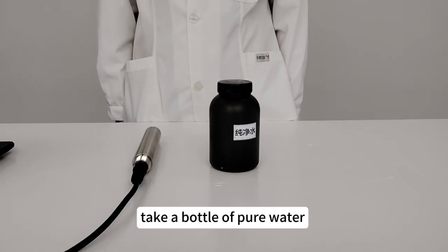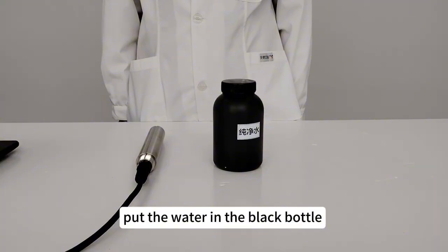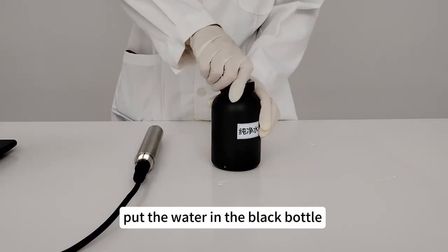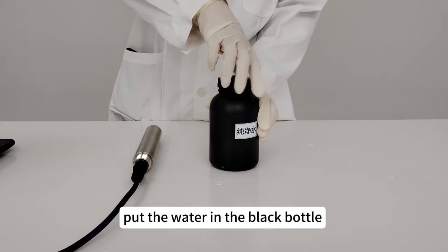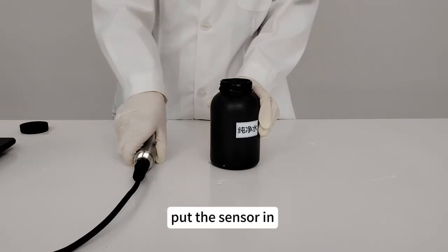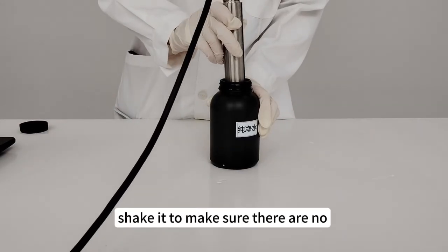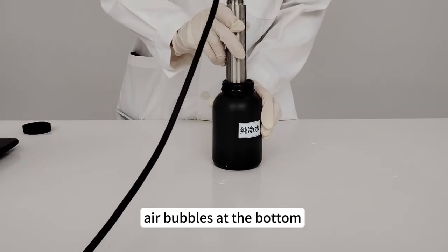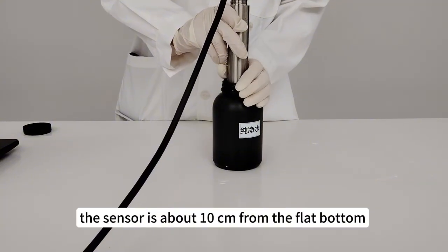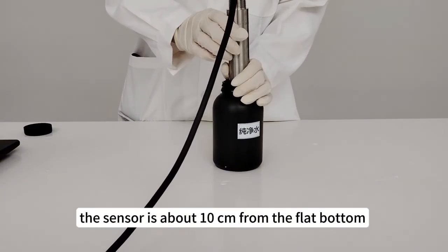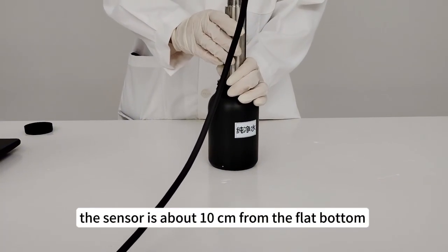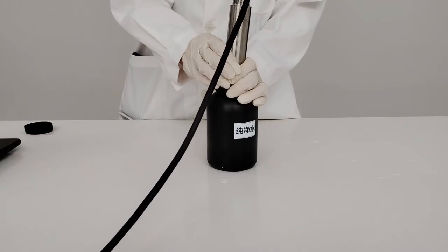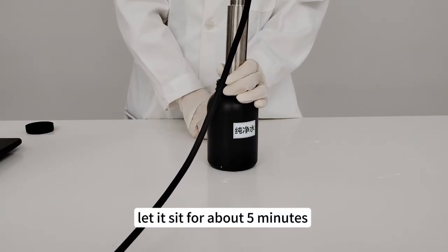Zero calibration. Take a bottle of pure water. Put the water in the black bottle. Put the sensor in. Shake it to make sure there are no air bubbles at the bottom. The sensor is about 10 centimeters from the flat bottom. Let it sit for about 5 minutes.